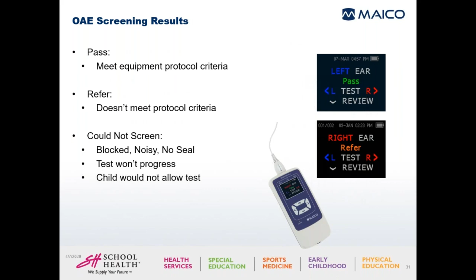And then another criteria that's set up in most devices is that 3 out of the 4 frequencies must pass. So if I'm looking at this last column, I see that I have a P next to all the frequencies that I tested. And so I know that this is a good pass result. So that's what this numerical information will provide to you. This is the protocol that is set up within the device. So you'll just want to look at the device that you have and the protocol that you're using, and make sure that it's consistent with what I have shown here.